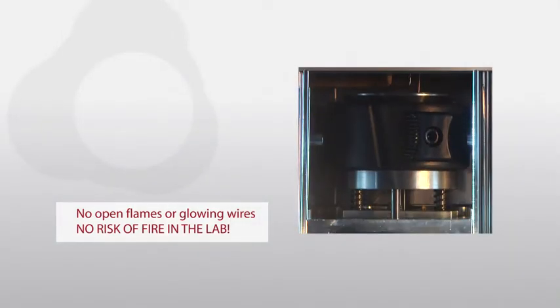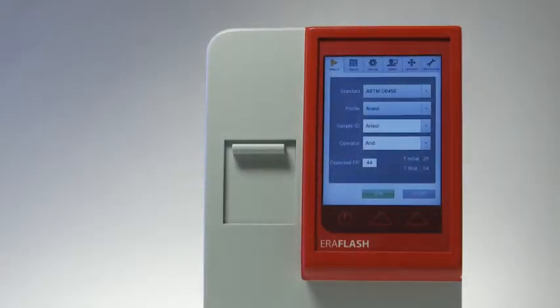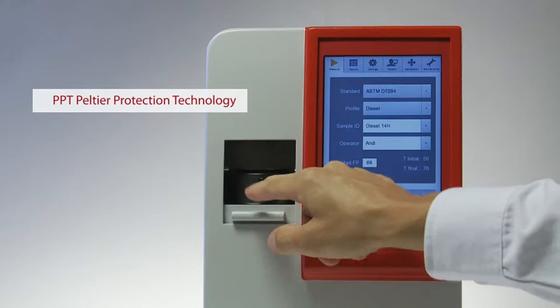There are no open flames or glowing wires in the EraFlash — the safest way to prevent the risk of fire or hazardous fumes in the laboratory. For your convenience, EraFlash also offers several pre-programmed correlation methods that provide results in excellent correlation to the traditional closed-cup methods such as Tag, Pensky-Martens, and include flash/no-flash methods.